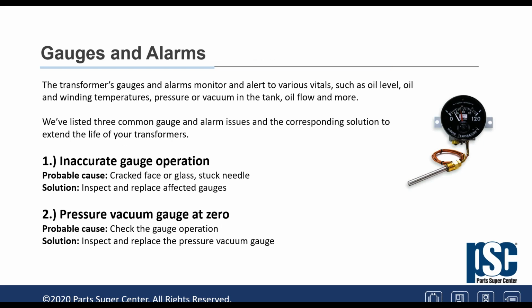Gauges and alarm. Again, we put the gauge. That's the only way we can keep an eye on a unit and see what's happening. Needless to say, a cracked gauge or a stuck needle is another typical problem, since these gauges are outdoors and subjected to the moisture and dirt of the air. Most of the time the needle gets stuck and doesn't show any changes. That's to prove that something is wrong. I mean, it's very seldom that a temperature or anything stays the same all the time.